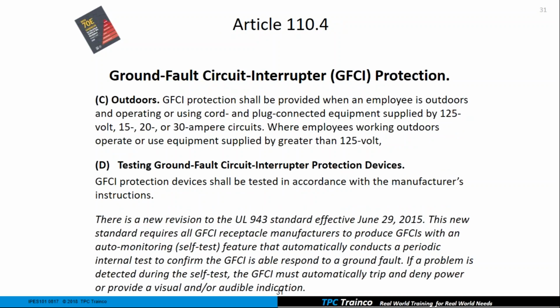GFCI. The thing that changed here is that there is a new revision to the UL Standard 943, and this requires all manufacturers to give us GFCIs with a self-test feature. So they're going to test themselves. We don't really have to test them, and if there is a problem when they go through their self-test, they are automatically going to trip and they are going to be de-energized. They are going to provide us with a light or some type of audible indication, but the manufacturer will now provide that to us. That is excellent because, let's face it, how many people went out and tested their GFIs every month like we're supposed to? So this is going to be very nice.